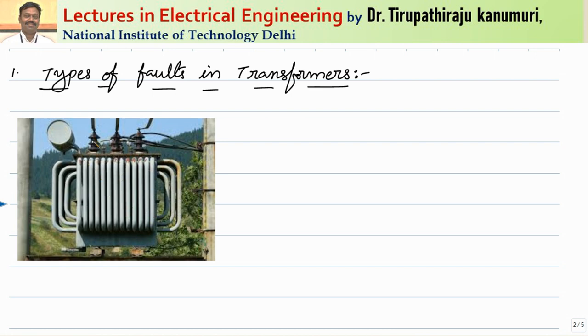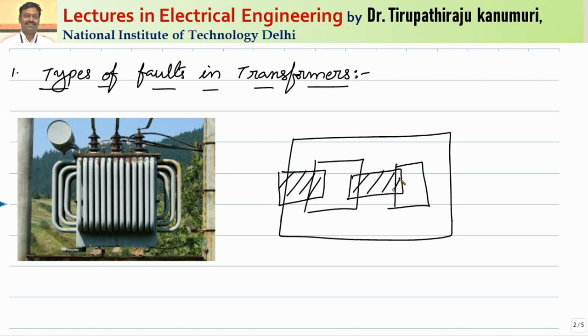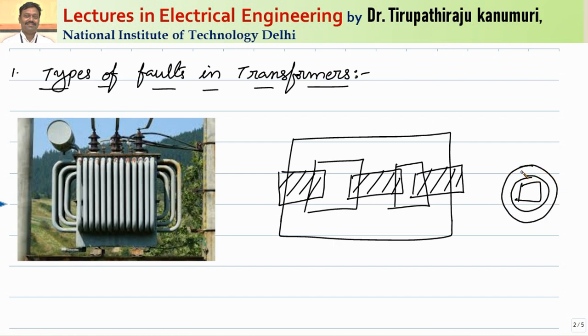There are cooling ducts for cooling purposes and terminals from which we can take the leads to the external terminals — these are also called bushings. Inside, for a core-type transformer, the winding is made on three cores with three different phase windings on three different cores. Seen from the top view, immediately after the core, the LV winding is placed first, and above the low voltage winding the high voltage winding is placed on the outside.